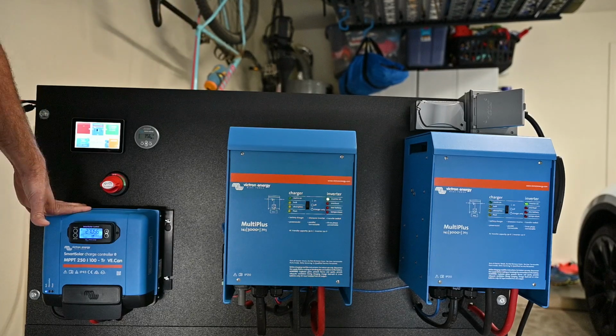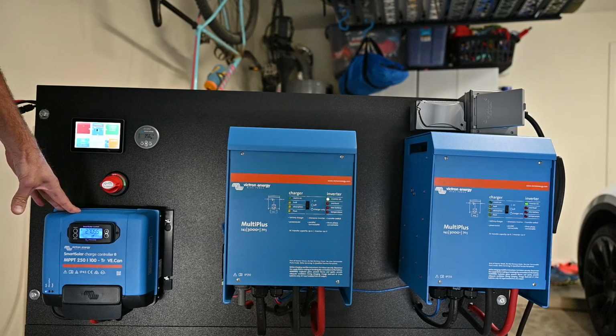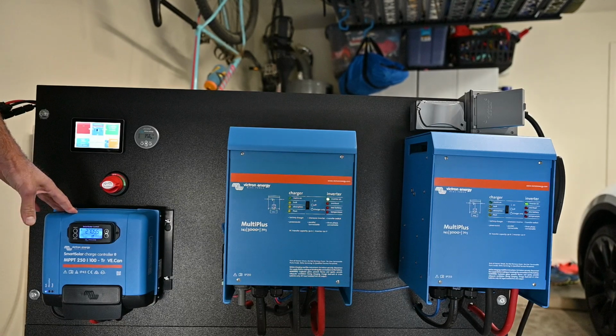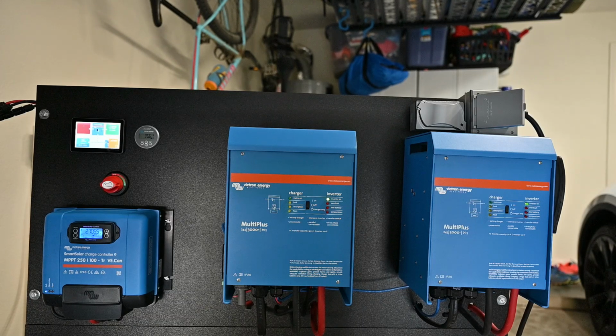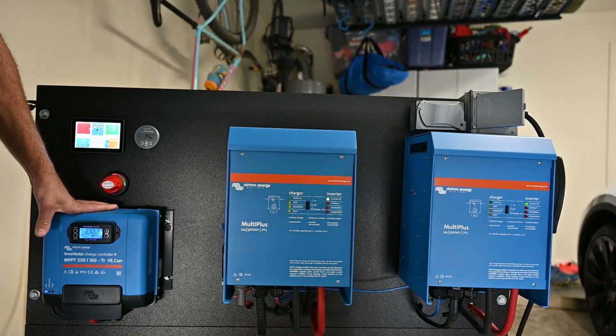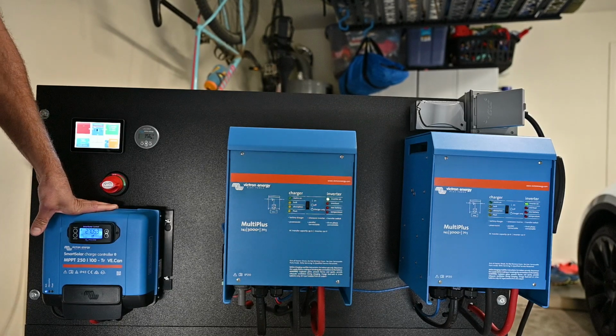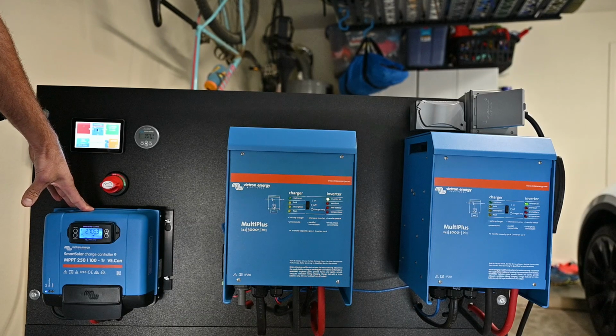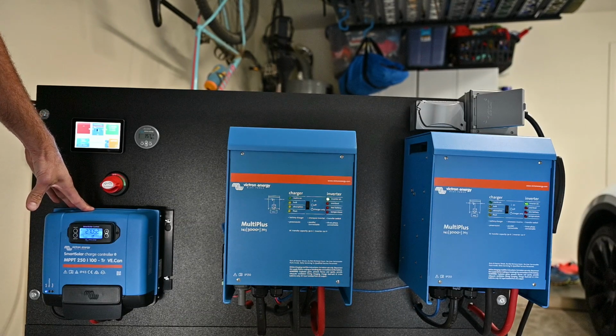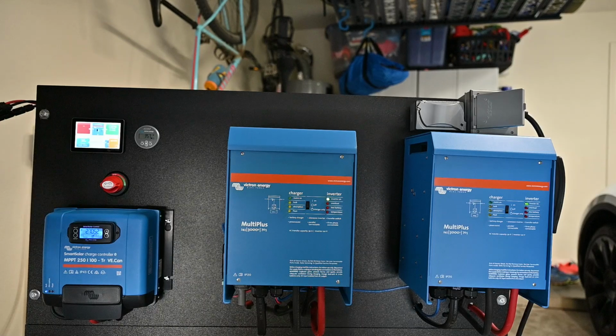I have a 24 volt system, and right now I'm outputting 2700 watts, because the battery voltage is at 27 volts, not 24 volts. So right now this is basically the peak power output for this single charge controller. If I wanted to increase my peak, I could get another charge controller, but right now this is sufficient.